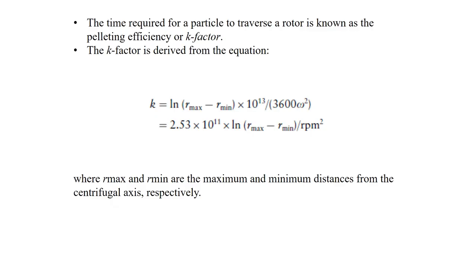The time required for a particle to traverse a rotor is known as the pelleting efficiency, or K factor. The K factor is calculated based on the maximum rotor speed and is a function of rotor design — different rotors have different K factors. The K factor provides a convenient means of determining the minimum residence time required for a pellet to separate, and it is very useful when comparing sedimentation time using different rotors.